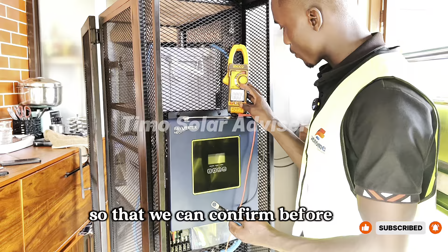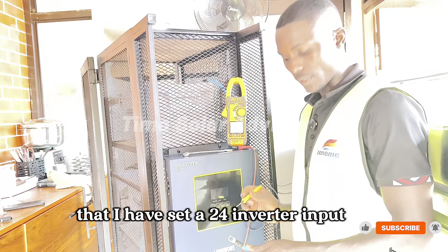We are using a clamp meter so that we can confirm before connecting to the inverter that I have set a 24 inverter input. As you see, this is the negative, I plugged in, and as you see it close, it is showing 26. Right now the batteries are full, so the setup is okay.